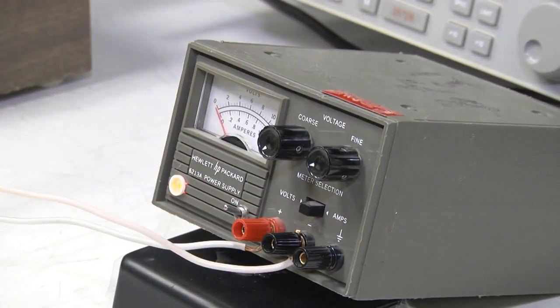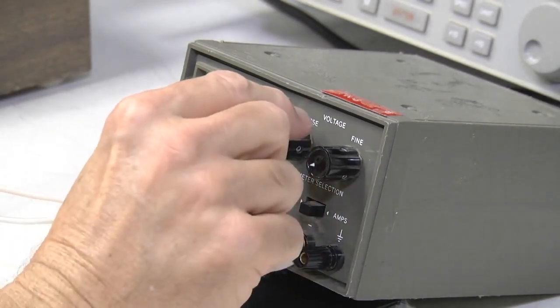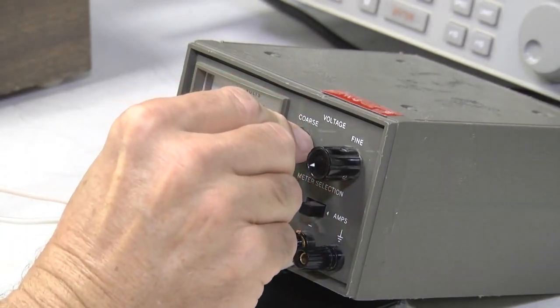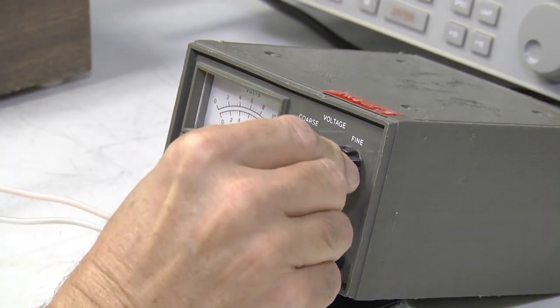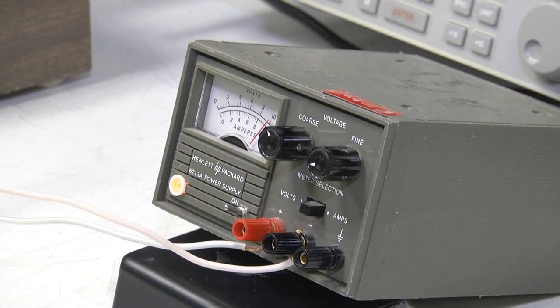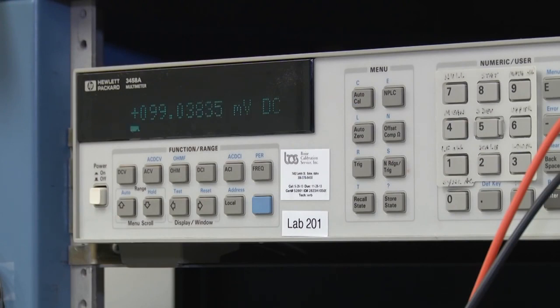We go ahead and turn the power supply on, and then we adjust the voltage output so that it indicates 1 amp on the output meter. Since we know the value of the current shunt, we can use Ohm's law and derive the actual current flowing through the circuit. The indication on the HP DMM up here is the voltage drop across the current shunt. By utilizing Ohm's law equations, E equals IR, and variations of that, we're able to calculate what the actual current through this is. This particular reading of 99.0 millivolts, using the calculation, tells us that the current flowing through here is 1 amp. That's indicated on the HP power supply, and the power supply is correct.